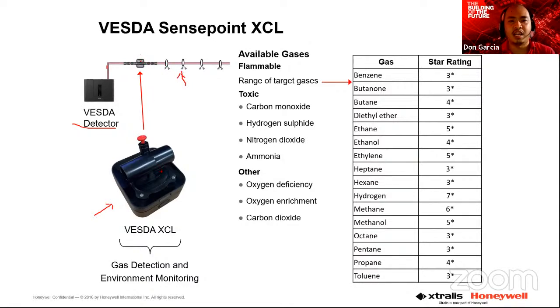The XCL will activate depending on the specific gas being monitored, for example ammonia, nitrogen, hydrogen, or carbon monoxide. As long as it draws in that gas, the gas detector activates based on a range value—it's not just alarm or normal, it gives you the actual value of the detected gas, like 100 ppm or 50 ppm, since it's already ranged.